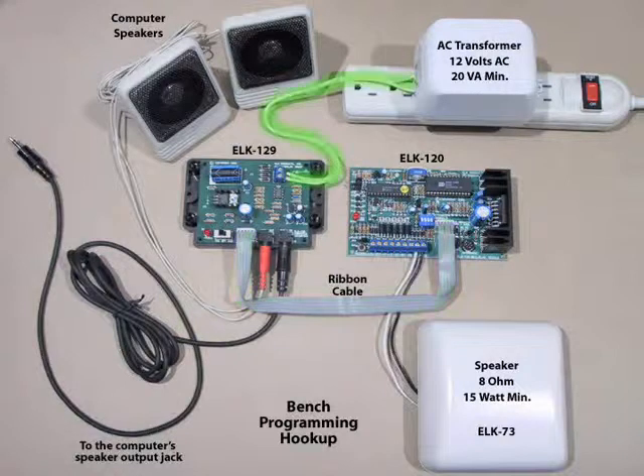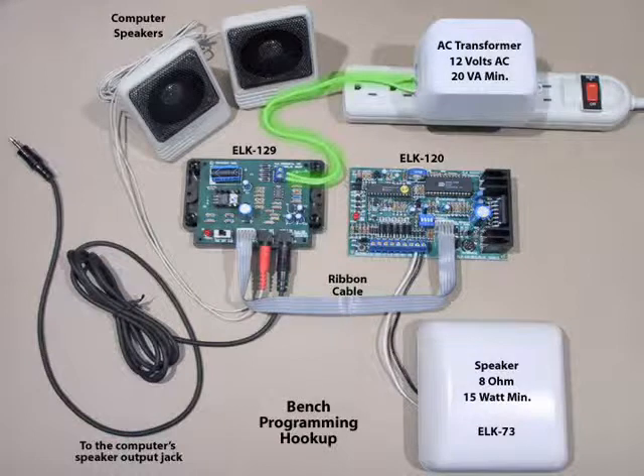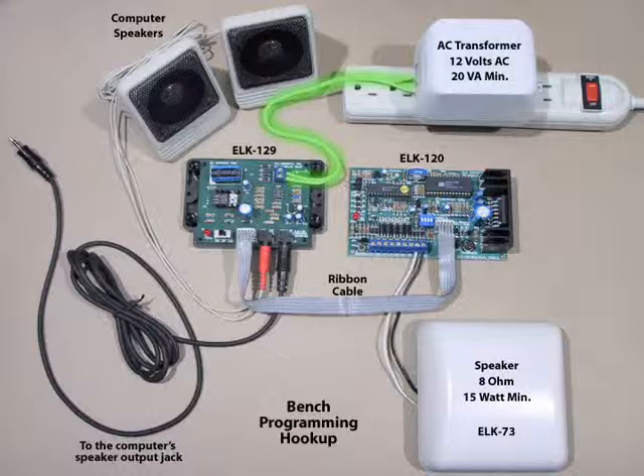Connect a 12-volt 20VA minimum AC step-down transformer to the AC terminals on the ELK 129, located under the cover. Then plug the transformer into an AC receptacle.